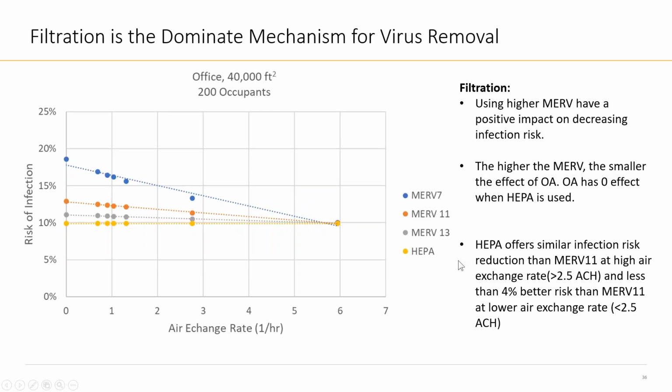This is the only slide I have with a graph, but basically, just to tell you, this slide should be taken as the risk of infection as relative, right? It's based on a series of assumptions, but the best thing we know today is to compare the relative risk of infection of different strategies. There's a series of assumptions: how many people are infected in your buildings, the layout of your buildings, etc. And I don't know if the asked question talks about MERV 11 versus MERV 13, but MERV 11 is in orange and MERV 13 is in gray.